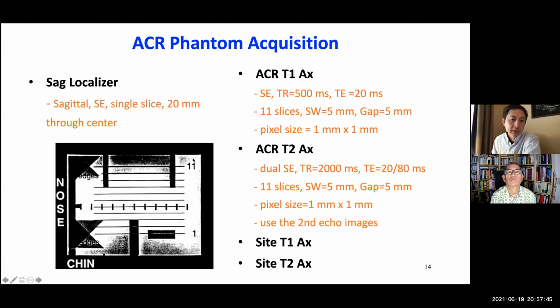And the proper scan of the ACR phantom includes at least 3 scans. First, a sagittal localizer. This is a single slice acquisition using a spin echo sequence. The image will look like that. Okay, so this is a chin, this is a nose. And then on this sagittal image, we prescribe the axial slices, 11 slices.